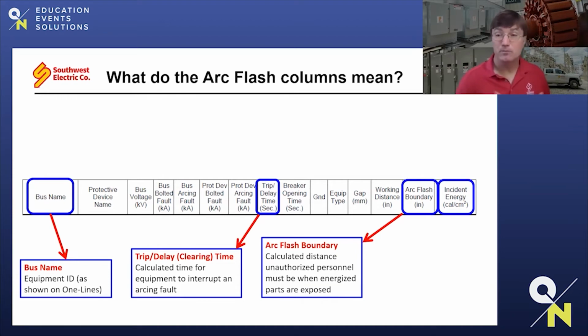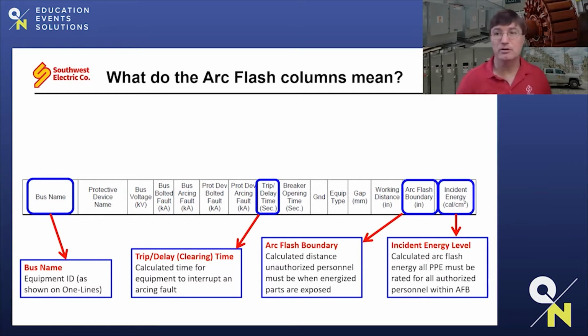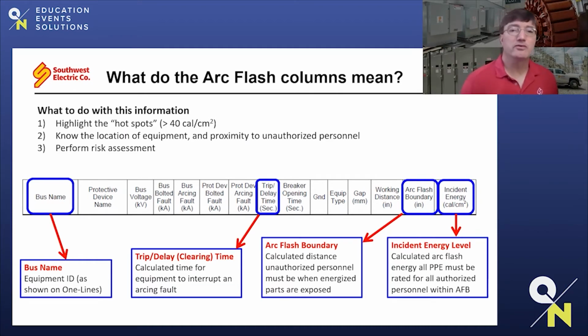The arc flash boundary we talked about earlier, that's the distance to keep non-authorized personnel who happen to be within the vicinity of exposed energized equipment, the distance they need to maintain to keep that 1.2 calories or lower protection. And then obviously the most critical is what is the actual incident energy level that's being calculated should a bus fault or an arc fault occur at this piece of equipment. Then the highlights of this section that we're going to look at is to highlight what the hotspots are. What are the incident energy levels that are the highest, especially those that are over the 40 calorie per square centimeter threshold.